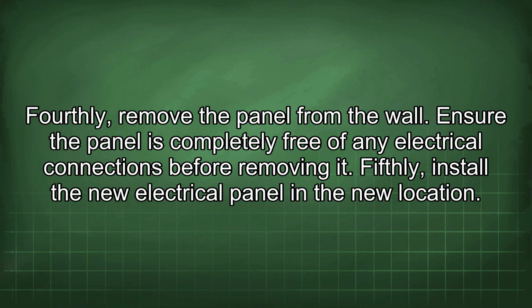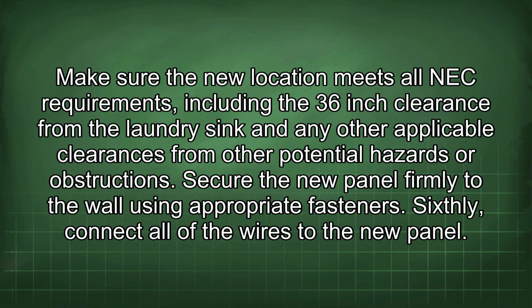Fifthly, install the new electrical panel in the new location. Make sure the new location meets all NEC requirements, including the 36-inch clearance from the laundry sink and any other applicable clearances from other potential hazards or obstructions. Secure the new panel firmly to the wall using appropriate fasteners.